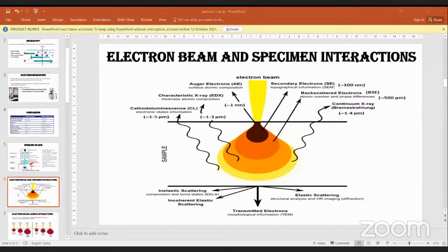But we have to be careful about the conductive paint that we use. Sometimes for liquid samples, we don't go for this carbon tape. We place the aluminium paint, and then a glass cover slip is placed on that, and on that one drop of your liquid sample, and then it is air dried. So the conductive paint should not come over the surface to be scanned. It should be underneath only. It shouldn't come on the surface.